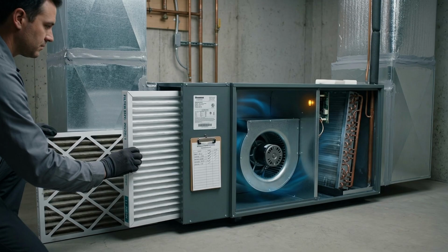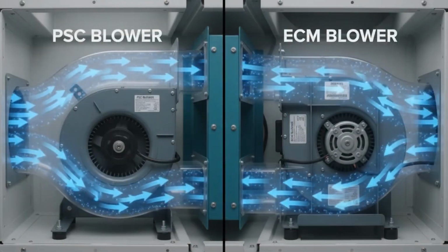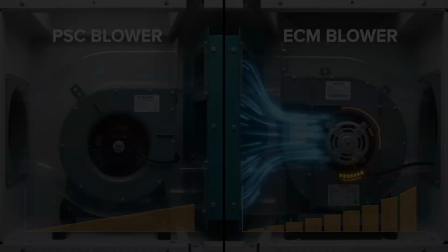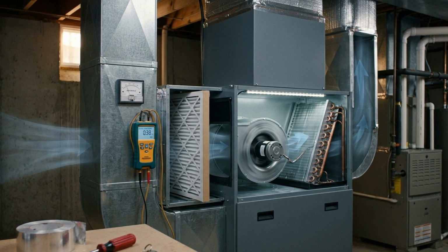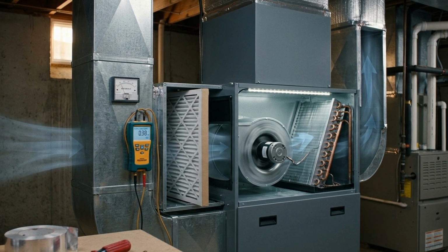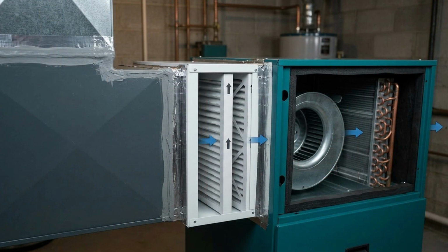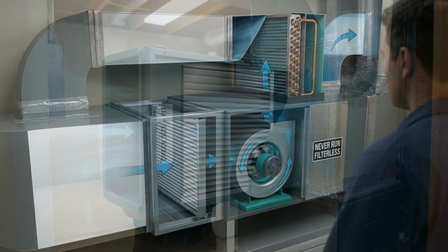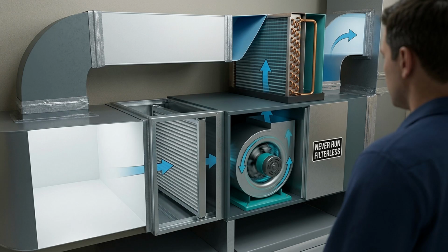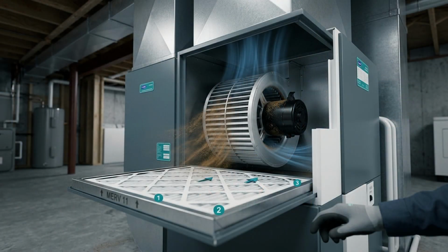The blower matters too. With a traditional permanent split capacitor, or PSC, blower, airflow commonly falls as external static pressure rises. A constant airflow electronically commutated motor, or ECM, may increase speed and power draw in an effort to maintain airflow, but only within its design limits. Neither description predicts what every installed system will do. A duct system that was already restrictive can leave little room for added resistance. A generously sized return, a large filter cabinet, and a filter with more media area can produce a very different result. The filter, blower, coil, and ducts have to be treated as one connected air path.